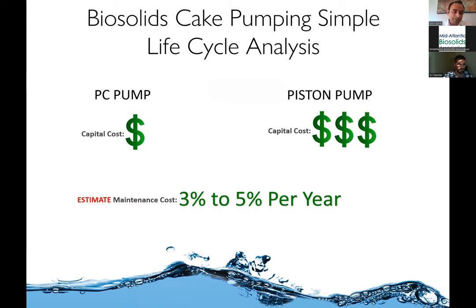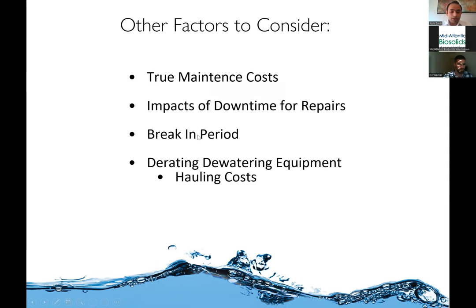As I mentioned, it's sometimes oversimplified. When we do this calculation, the capital cost for the piston pump is very high compared to the PC pump, and then we take 3-5% of capital cost as the maintenance cost. Then of course, in a 10-year life cycle cost analysis, PC pumps become the most economical. However, if we look at the true numbers, the actual data, that is not always true.